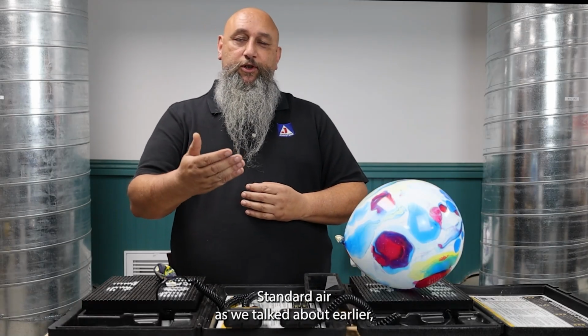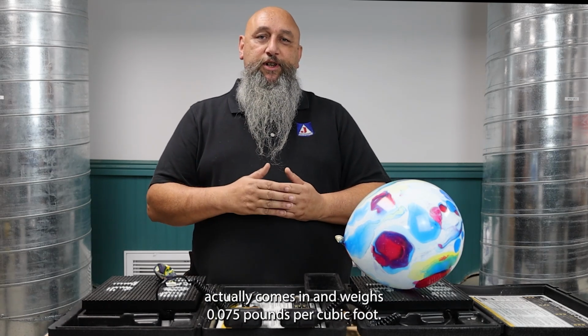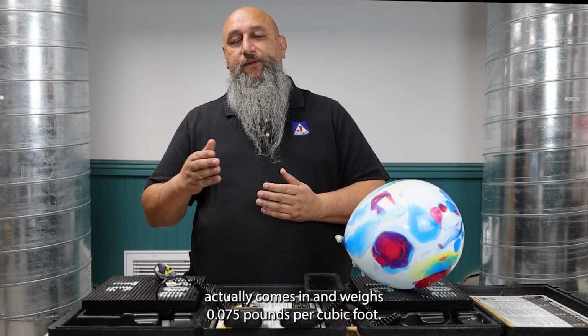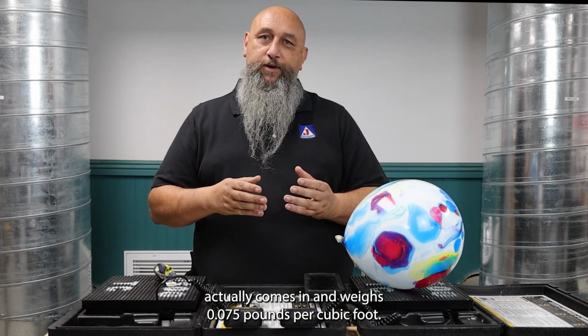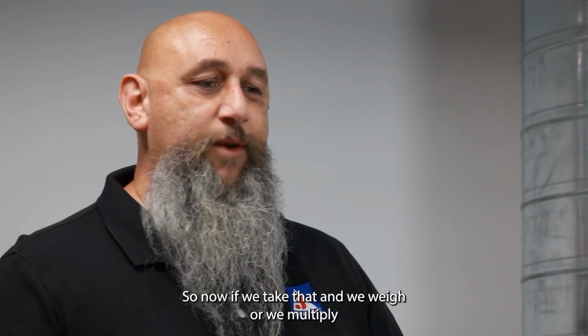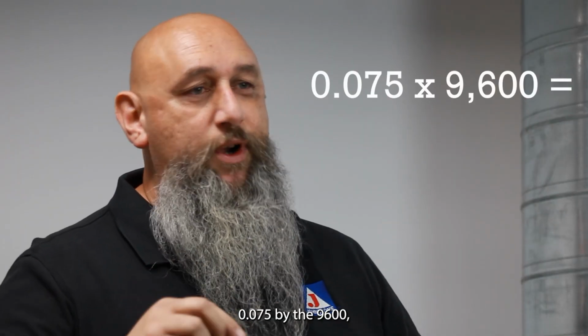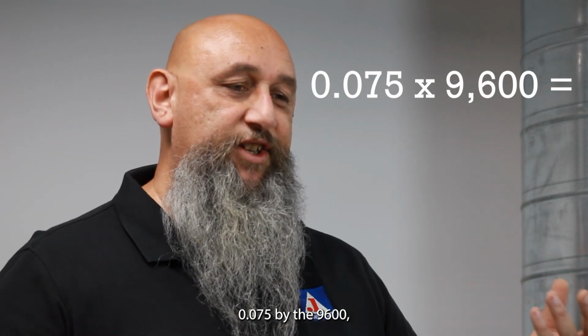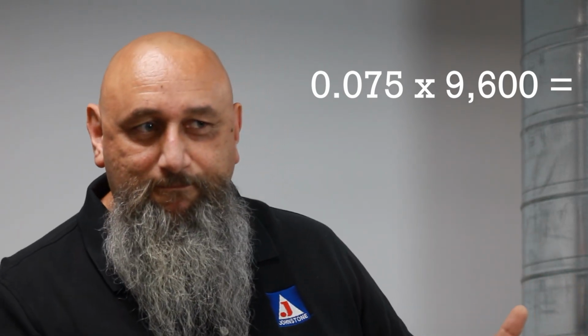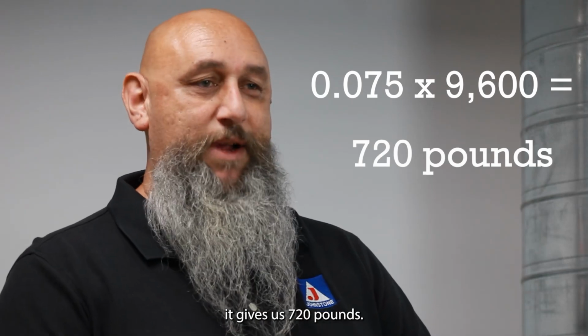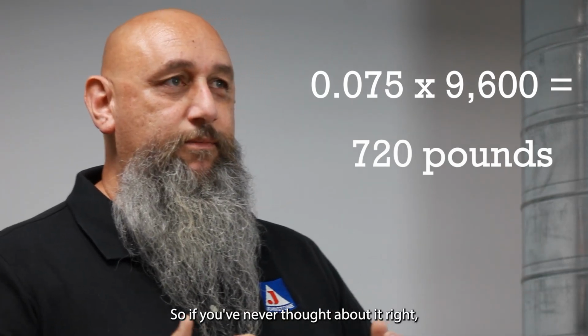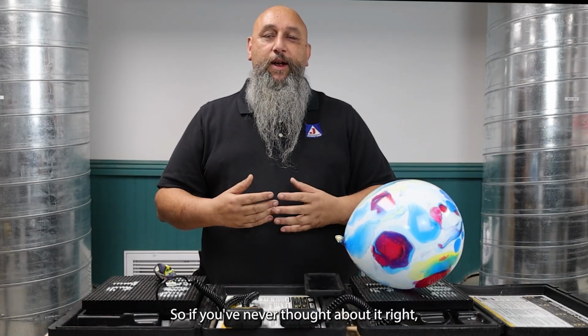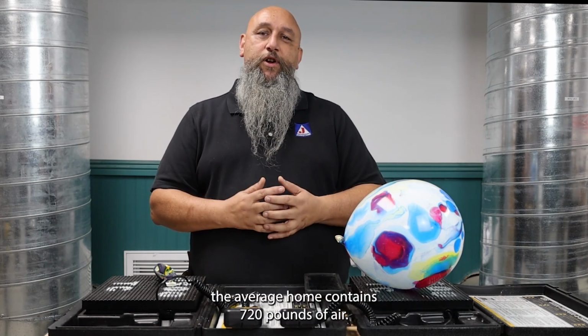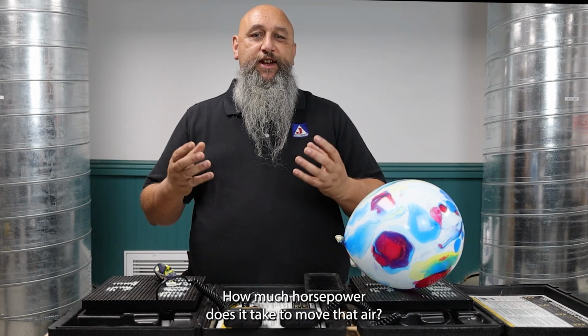Standard air, as we talked about earlier, weighs 0.075 pounds per cubic foot. So if we multiply 0.075 by the 9,600, it gives us 720 pounds. So if you've never thought about it, the average home contains 720 pounds of air. How much horsepower does it take to move that air?